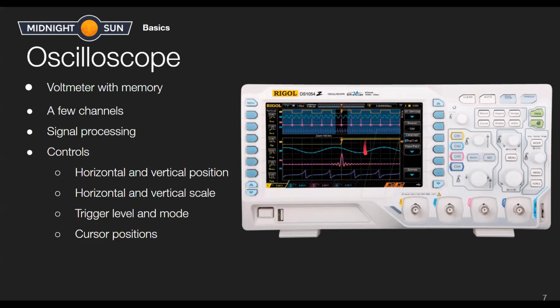Yeah, one more thing is that once you have an image, you can activate cursors using a button that's labeled cursors. This will place 2 cursors on the waveforms, and you have to tell it which channel to place them on. Then there will be a little box that will tell you the voltage and time at each cursor position, and it will automatically calculate the difference in voltage or the difference in time. It will also automatically calculate the frequency, just by taking the inverse of the difference in time between the cursors. So if you measure a sinusoidal waveform like this blue one here, you could put one cursor at the beginning of a cycle and one at the end of a cycle, and then it'll tell you the frequency of that waveform.